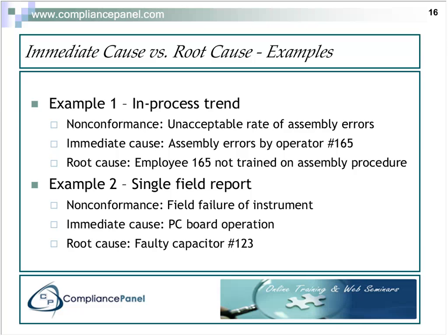The second example, as opposed to in-process, is a field report, and as opposed to a trend, is a single occurrence. So you have a particular instrument for which you receive a complaint that it's not working for a particular reason. The instrument is failing in the field. Well, either when the item is returned to your firm, or maybe troubleshooting with one of your service people out in the field, you determine that the PC board is not operating correctly.